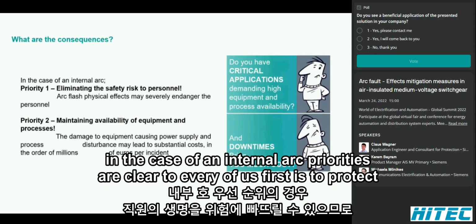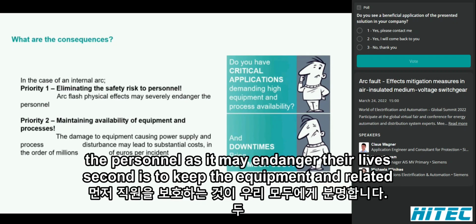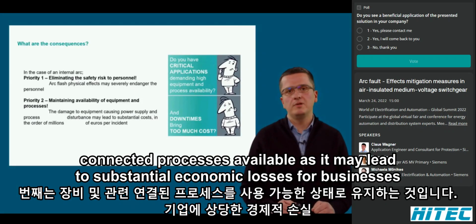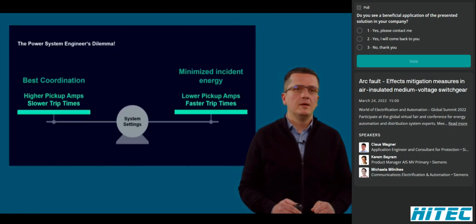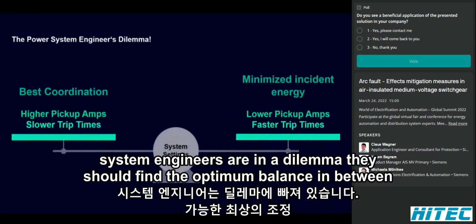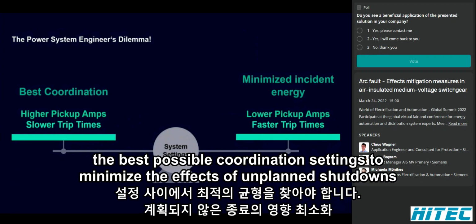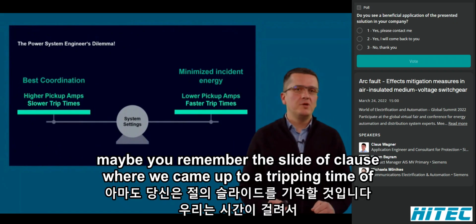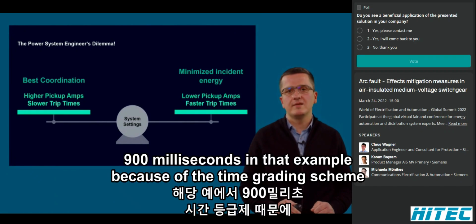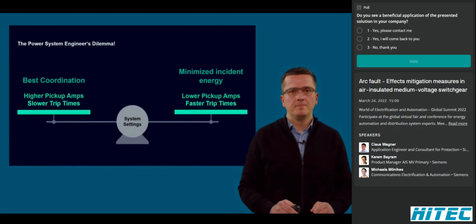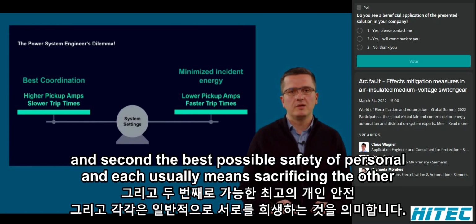priorities are clear to every one of us. First is to protect the personnel, as it may endanger their lives. Second is to keep the equipment and related connected processes available, as it may lead to substantial economic losses for businesses. System engineers are in a dilemma. They should find the optimum balance between the best possible coordination settings to minimize the effects of unplanned shutdowns. Maybe you remember the slide of Klaus, where we came up to a tripping time of 900 milliseconds in that example because of the time grading scheme. And second, the best possible safety of personnel. And each usually means sacrificing the other.